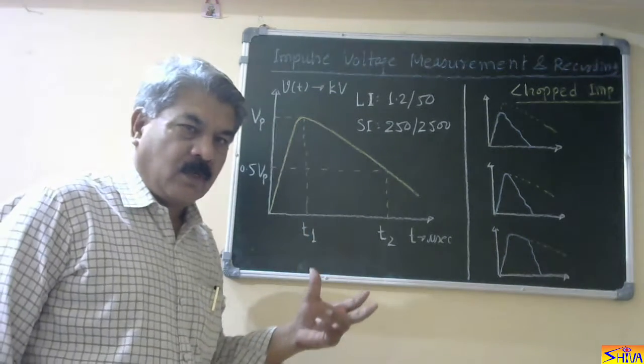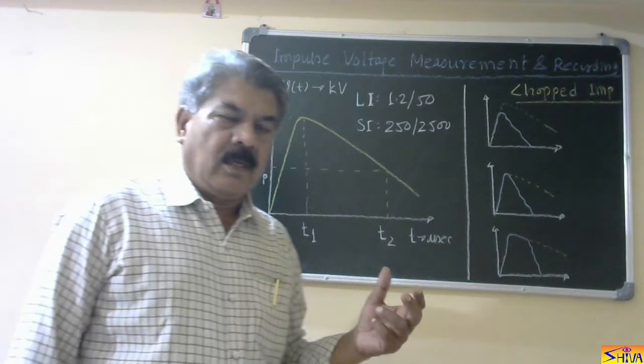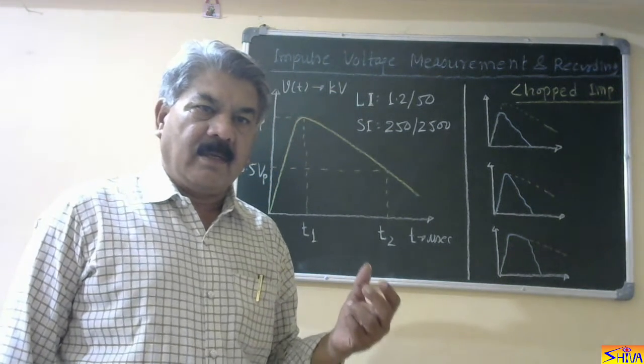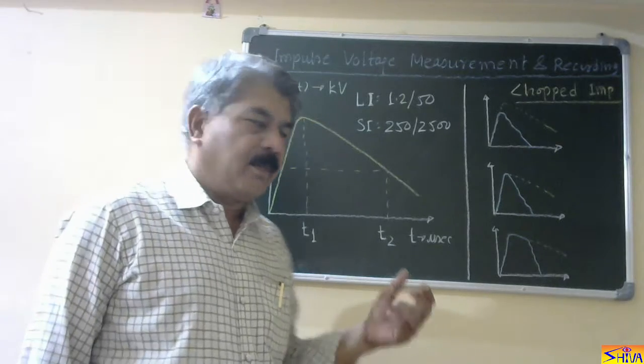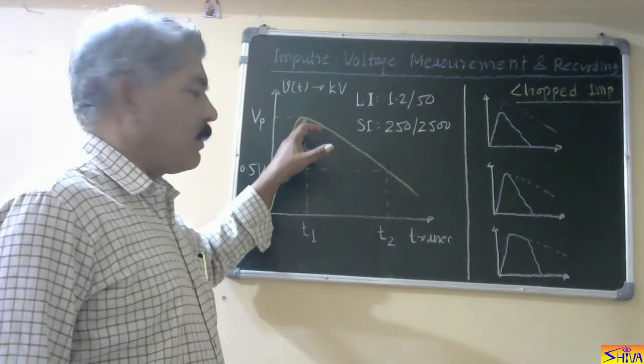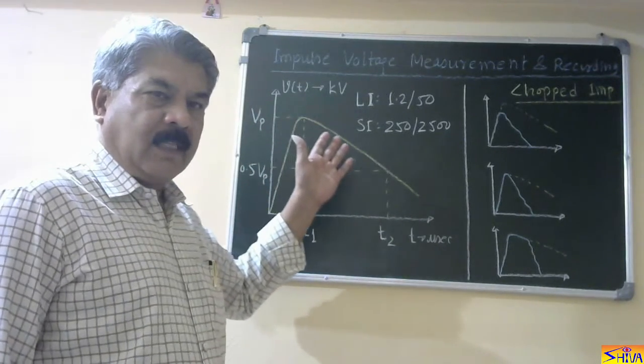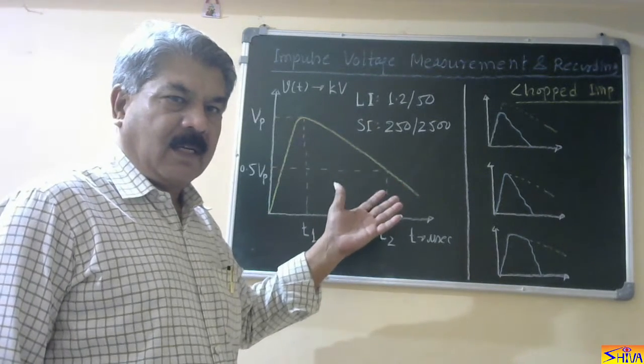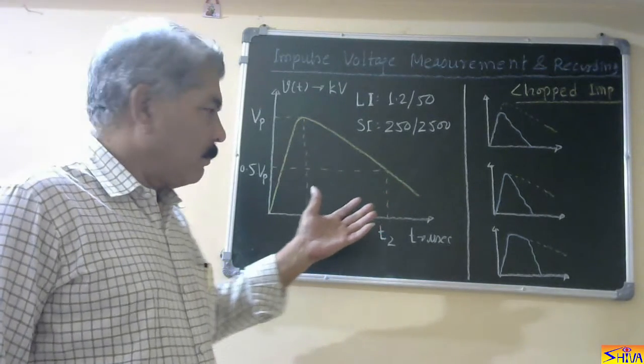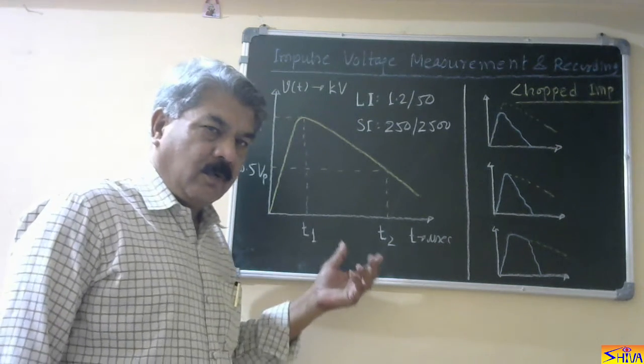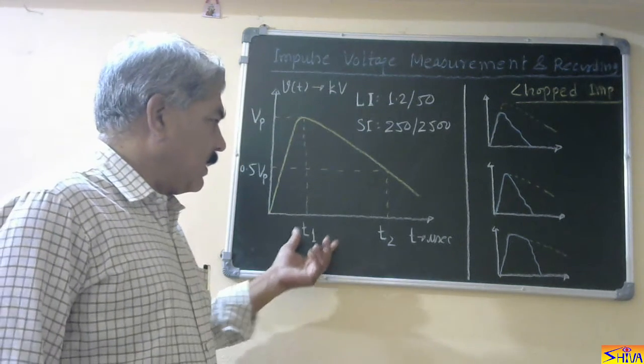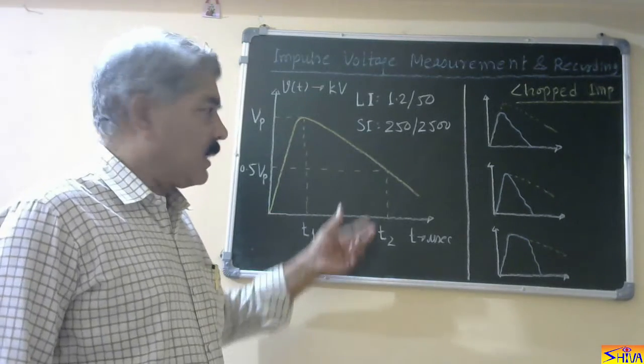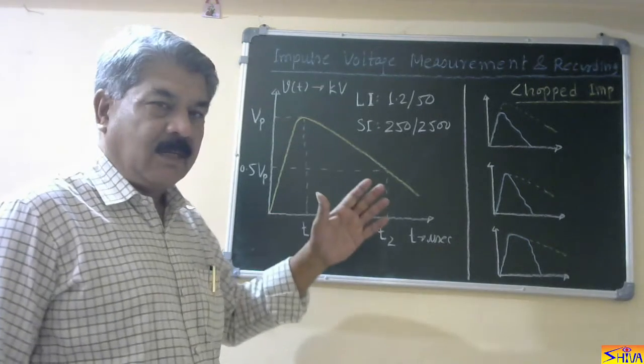Now, this is a one-shot voltage. So, only measurement will not be sufficient because when we measure, we can know how much was the peak value. This we can know by the peak reading voltmeter, sphere gap arrangement, or potential divider also. But we will not come to know whether it is as per standard or not. We require the wave as per standard with certain tolerances.